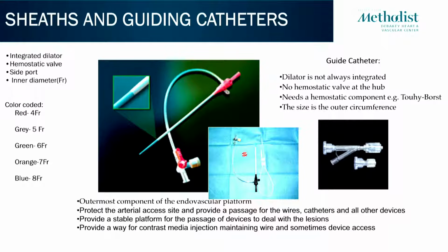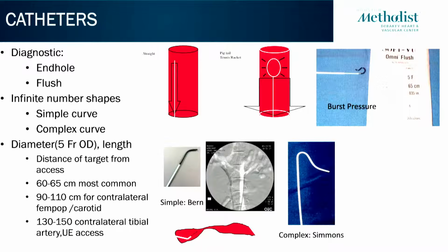A guide catheter is a little different. It's like a sheath, but it doesn't have a hemostasis valve on it, so you got to put one on it, and it's sized according to its outer diameter. And so one of the ways you put a hemostasis valve on it is to put on what's called a Y-adapter. So this is a side port, and this is an adjustable valve. It's one of these valves that you can take off the shelf, you can put it on there. So for example, when we deploy coils, the coils that Boston Scientific have, basically you deploy them through one of these Y-adapters. And so you need to get to use and play with one of these.